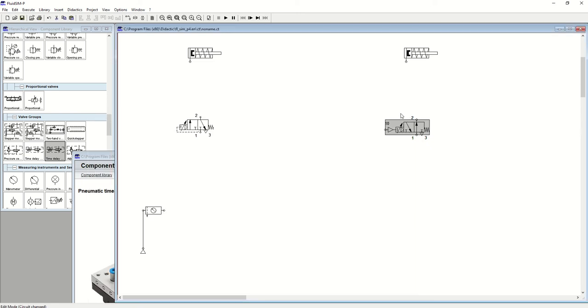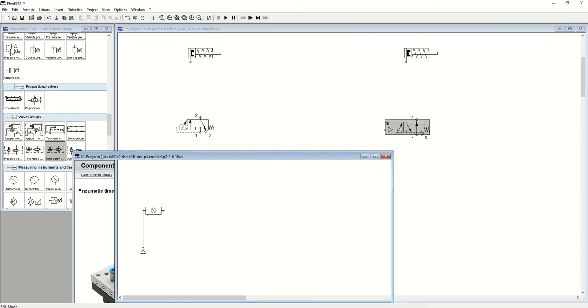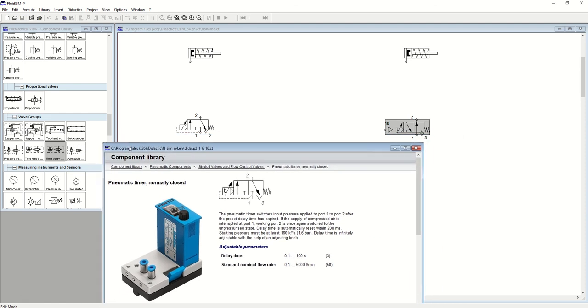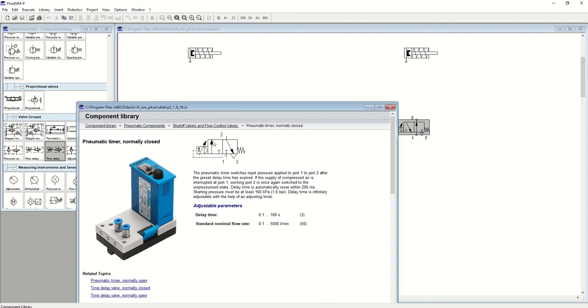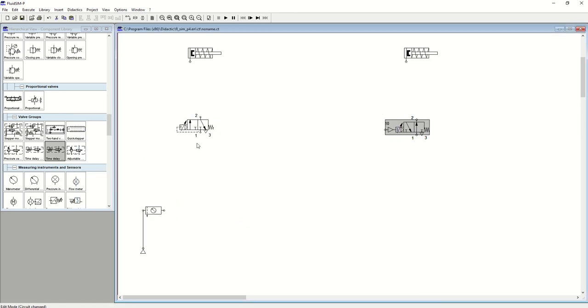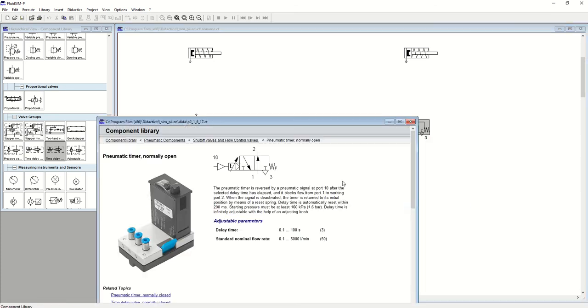There's another wording if that wasn't confusing enough - you've got an on delay timer and an off delay timer, which I explain more within the symbols themselves. The normally closed timer is blue in the Festo catalog with a nice dial where we can see what we're setting the value to. It has two ports we need to connect, port one and port two, and three is just an exhaust. With the normally open one that's black symbolism, we've three ports that we connect to, excluding the exhaust.